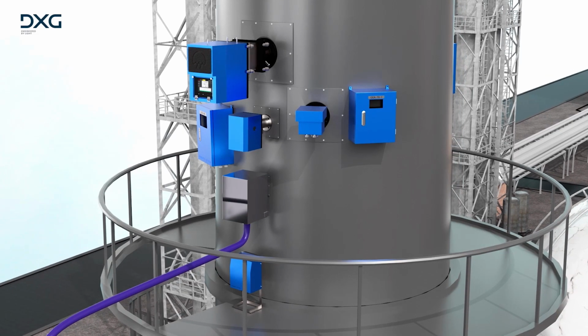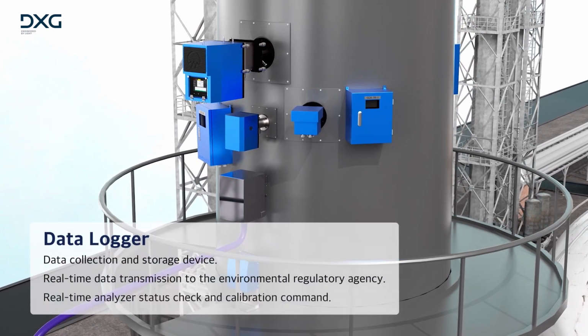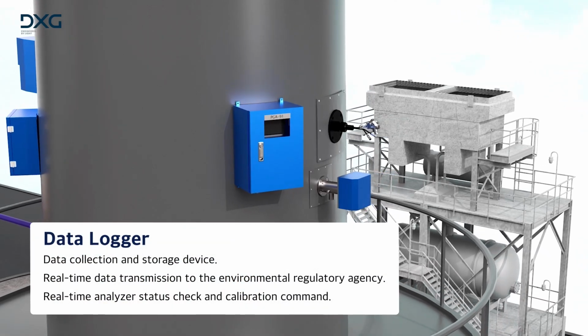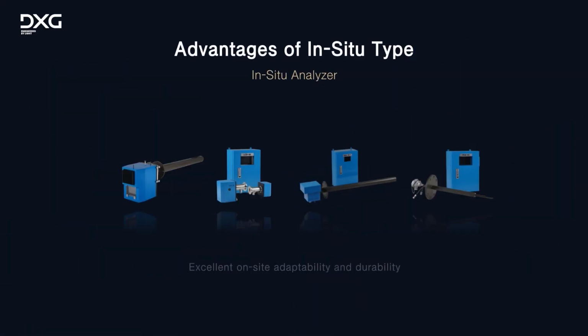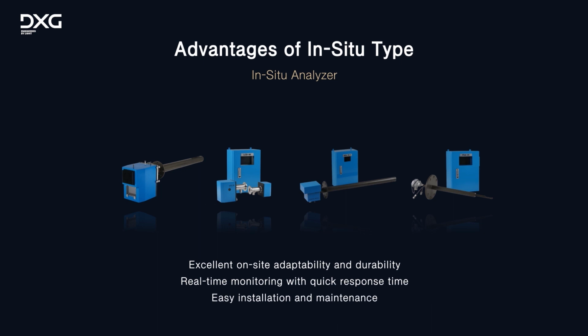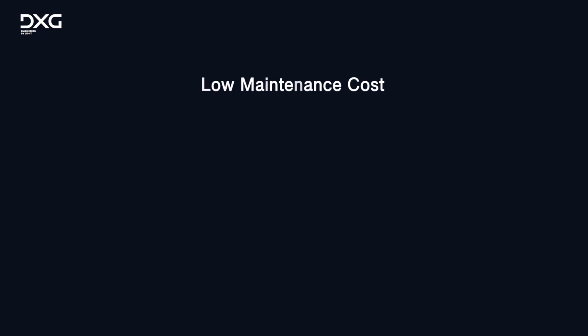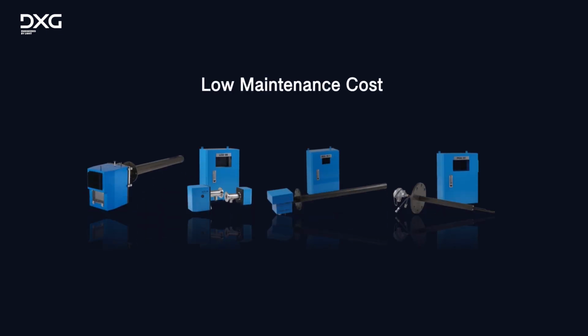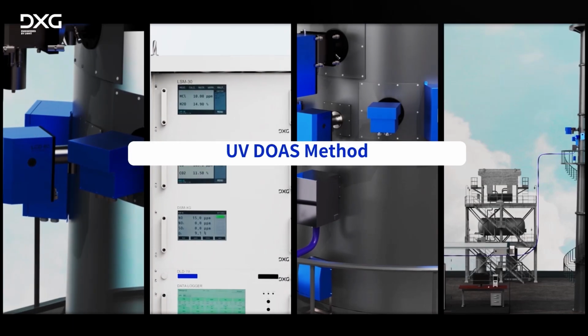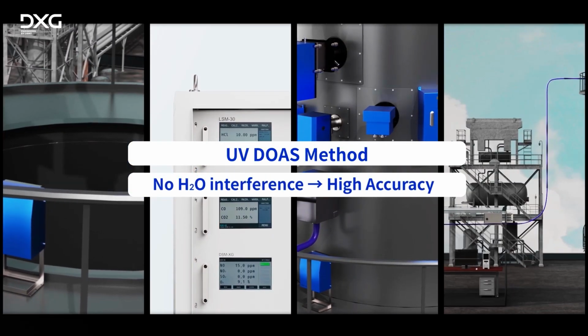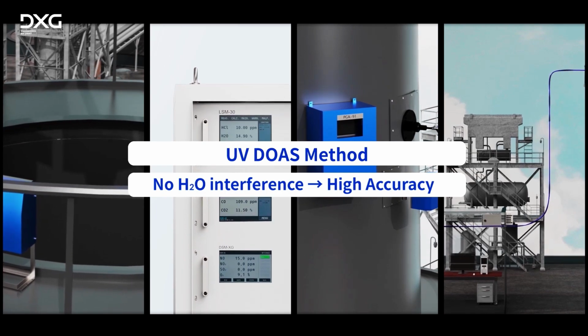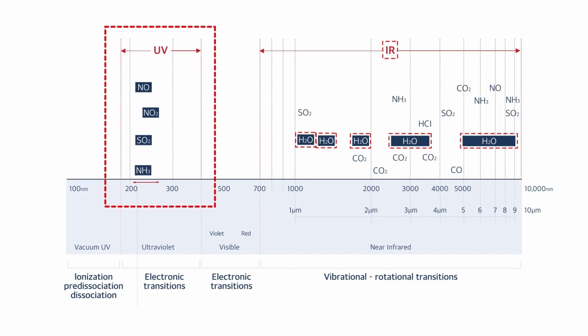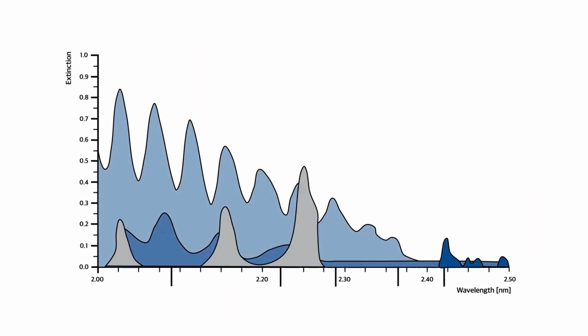Once the analysis is completed, emission data will be transmitted to the Environmental Regulatory Agency through the data logger. The In-situ type does not extract the gas from the chimney, and thus does not need a complicated sampling and conditioning process. Also, with a compact and simple configuration, the In-situ type features simple installation and maintenance. DXG's UV DOAS analyzers can be an effective remedy for the drawbacks of traditional NDIR analyzers, such as poor precision, low concentration measurement, and H2O interference.